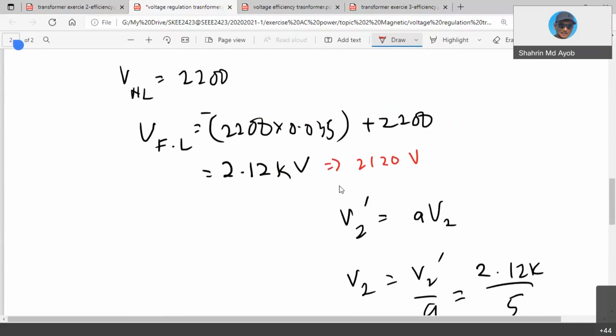V no load is 2200, but when you connect a load, the voltage drops a little bit, from 2200 to 2120 volts, which makes sense because there is a voltage drop — we have the internal resistance and the reactance, so definitely there will be a voltage drop. But the value of the voltage drop depends on the resistance and the material used. If the material is very expensive and very good, usually the internal resistance is very small, and the reactance is also very small, meaning your voltage regulation is very good.